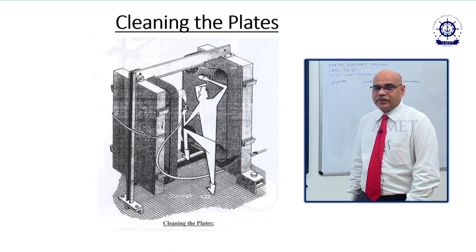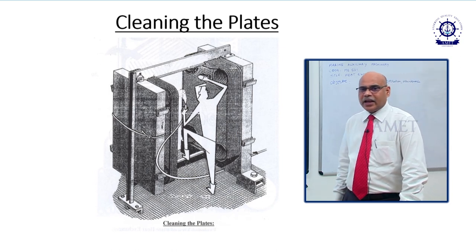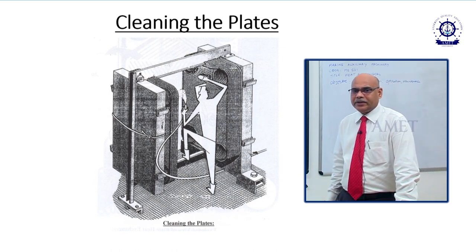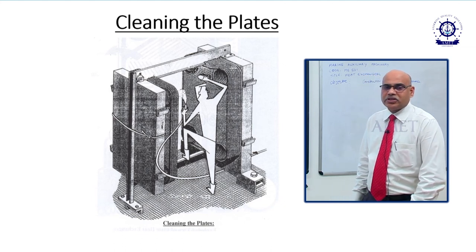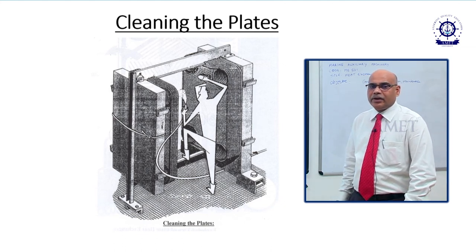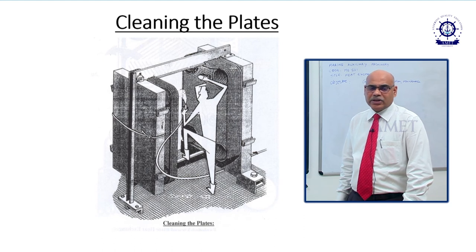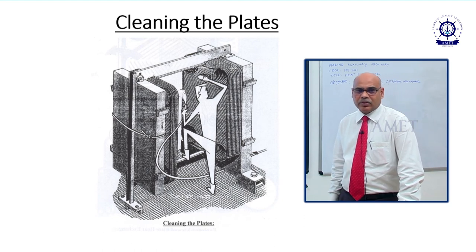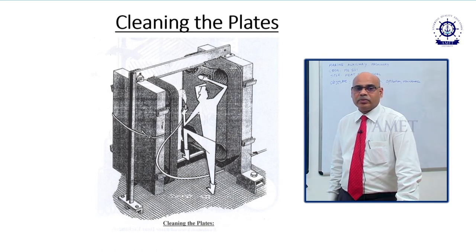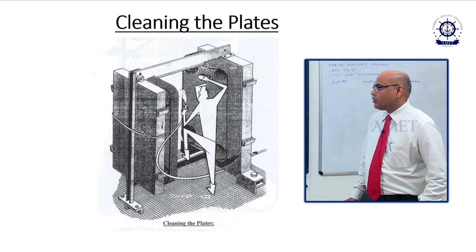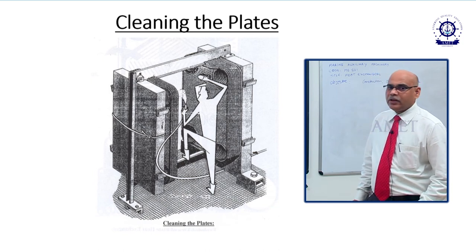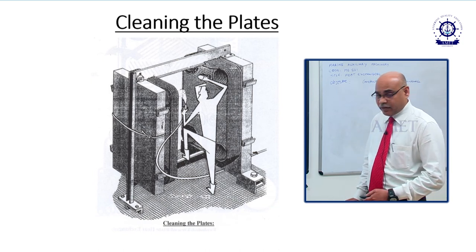If there is a leakage, the entire heat exchanger has to be removed, each and every plate has to be checked, and the damaged gasket has to be replaced — so it is a big task. One has to be very careful while doing maintenance.